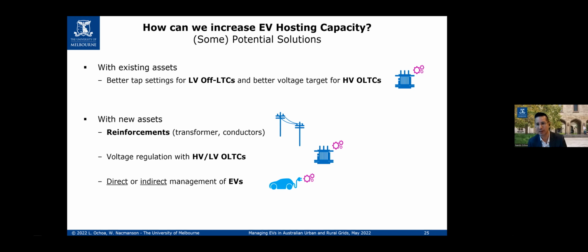Now, if you look at the on-load tap changer at the zone substation, there are a lot of opportunities to control and regulate voltages properly for photovoltaics situations, but also at night for electric vehicles. So it can be used, but that's just voltage. And as Will mentioned, and our results confirm, there's a lot of challenges with asset congestion. So whatever you do with voltage is great, but that's not the only problem—in fact, the first problem will be asset congestion.